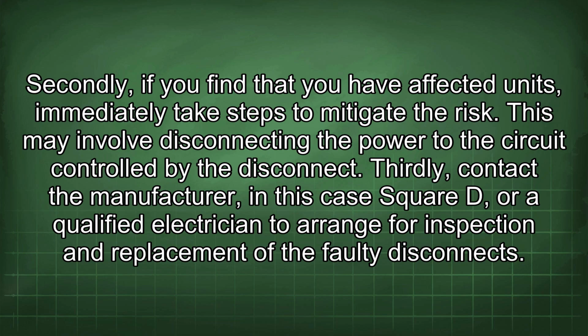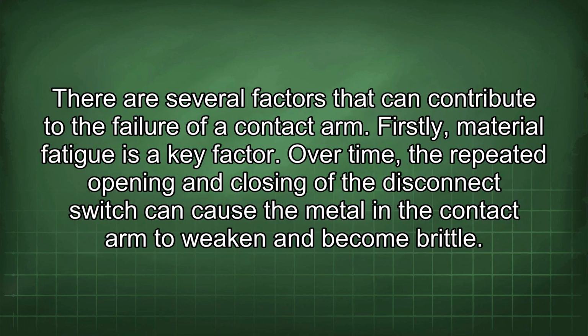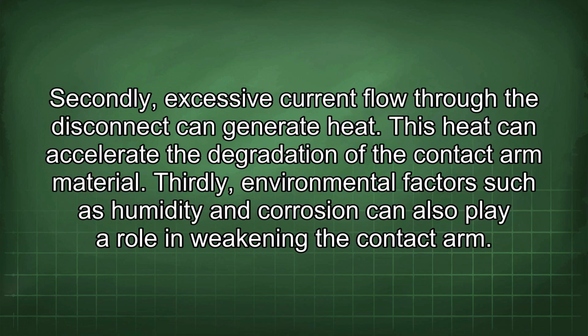the faulty disconnect. There are several factors that can contribute to the failure of a contact arm. Firstly, material fatigue is a key factor. Over time, the repeated opening and closing of the disconnect switch can cause the metal in the contact arm to weaken and become brittle. Secondly, excessive current flow through the disconnect can generate heat. This heat can accelerate the degradation of the contact arm material. Thirdly, environmental factors such as humidity and corrosion can also play a role in weakening the contact arm.